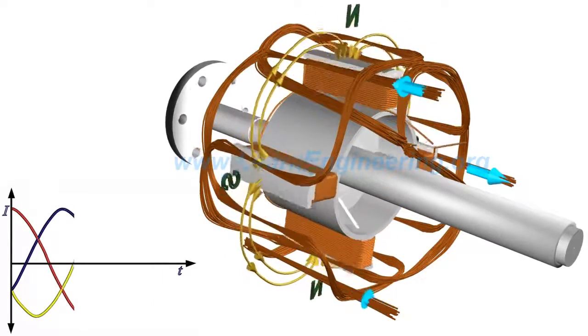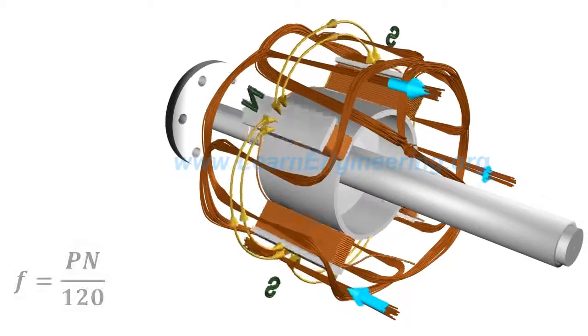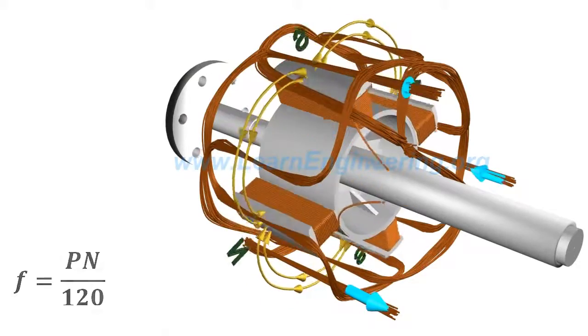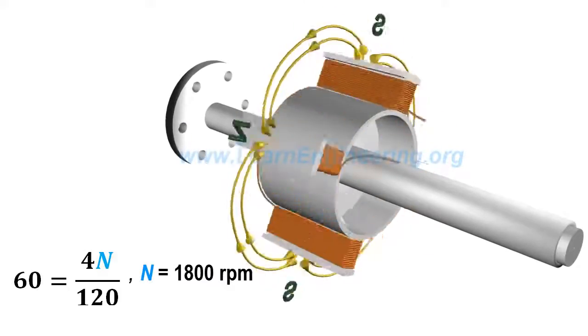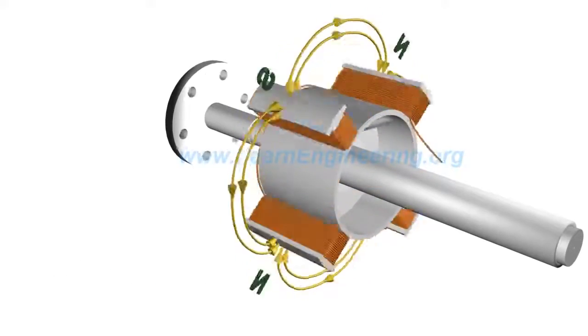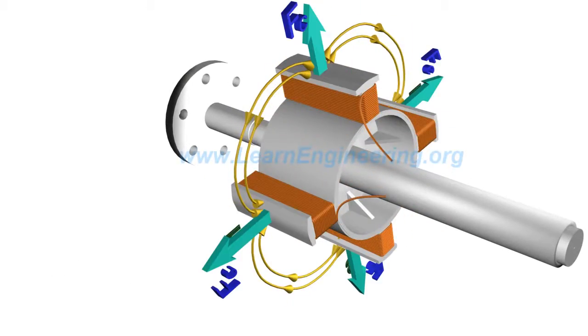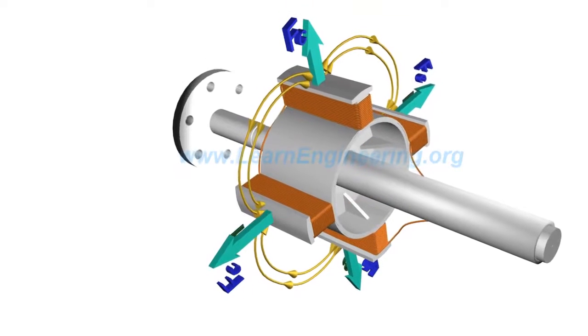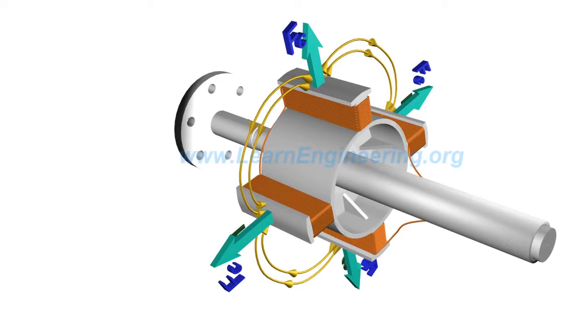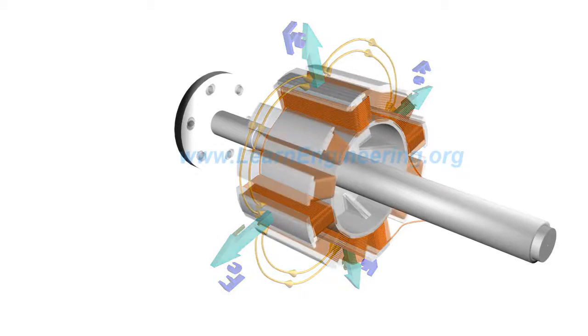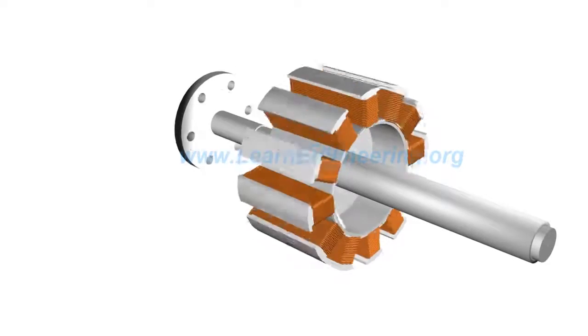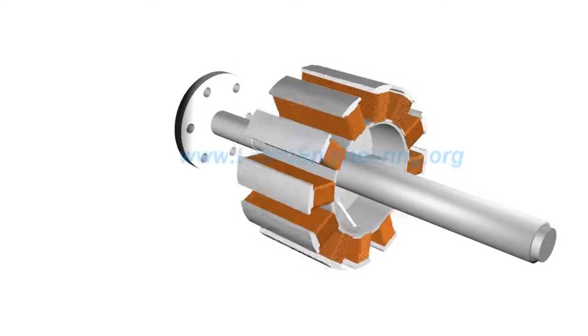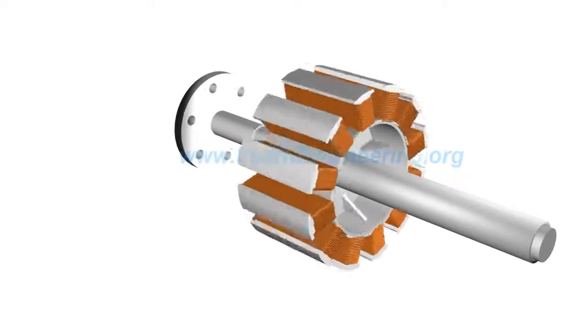It is clear from this equation that in order to produce 60 hertz electricity, a four pole rotor should run at a specific RPM. Such huge RPM will induce tremendous centrifugal force on poles of the rotor, and it may fail mechanically over time. So, salient pole rotors generally have 10 to 20 poles, which demand lower RPM. Salient pole rotors are used when the prime mover rotates at relatively lower RPM.